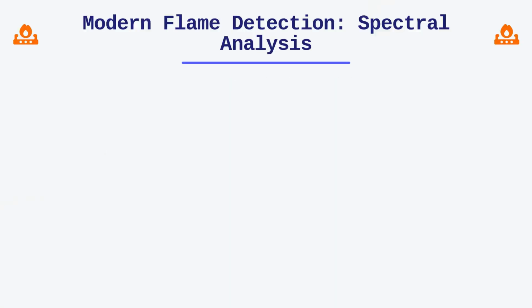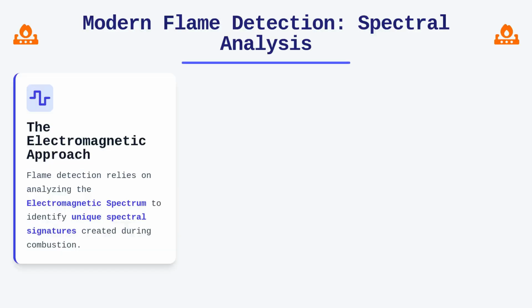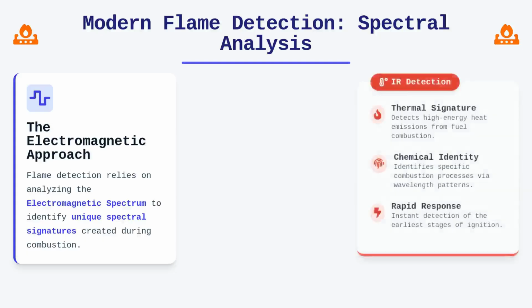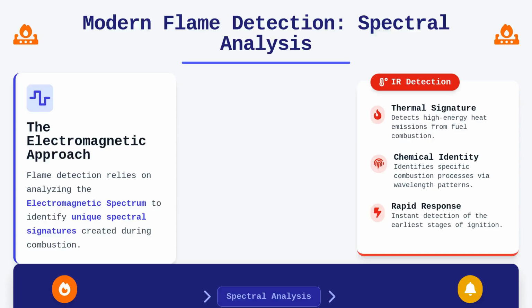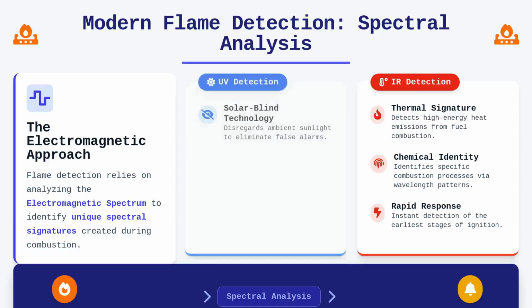To understand modern flame detection, we must first focus on how these devices interact with the electromagnetic spectrum. Ultraviolet and infrared sensors are the primary tools in our arsenal, each sensitive to specific wavelengths emitted by a combustion process. When a fuel burns, it produces a spectral signature that is unique to the chemical reaction taking place. Ultraviolet detectors are engineered to be solar blind, meaning they disregard the ambient sunlight that reaches the Earth's surface, which would otherwise trigger false alarms.